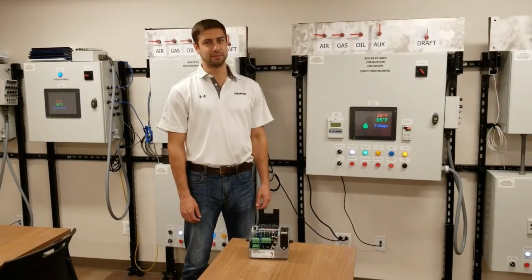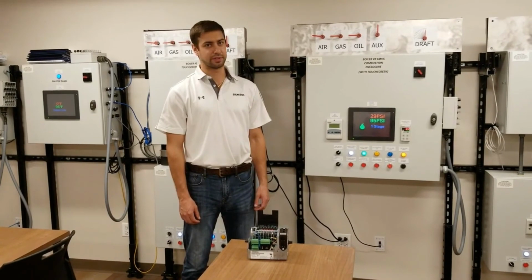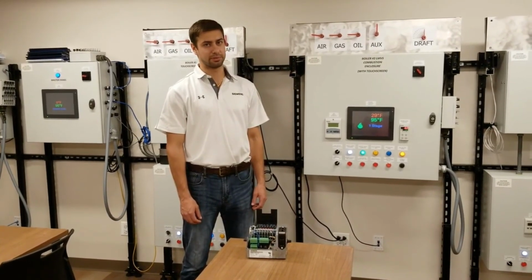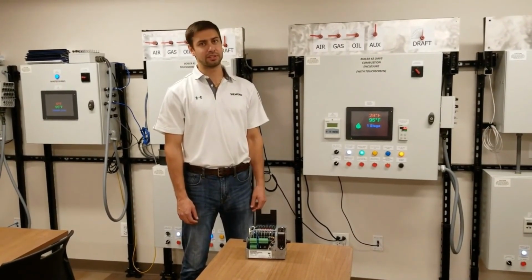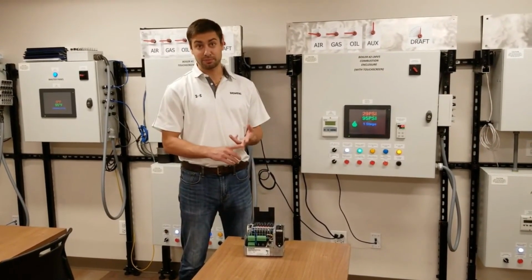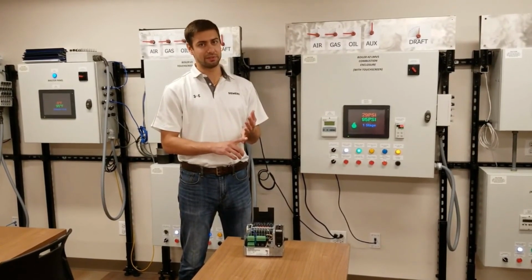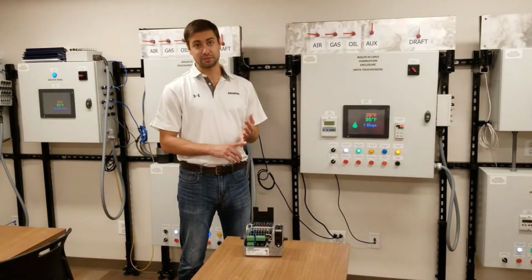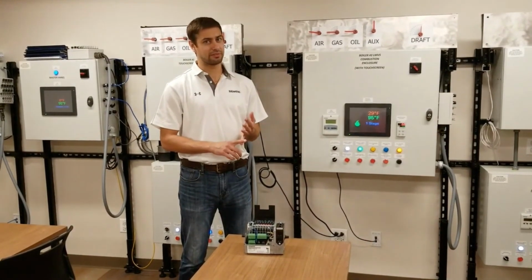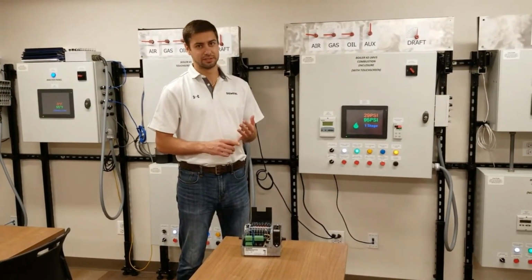Again with SEC. Today we're going to continue our discussion with the SQM5 actuator, and we're going to explore the Z board or multi-input option. With the Z board, you can use 0 to 20 milliamp inputs, 4 to 20 milliamp input, 0 to 10 volt input, and 0 to 135 ohm input. For this demonstration, we're going to assume that we're using a 4 to 20 milliamp signal and that the motor is on black scale. Let's get started.